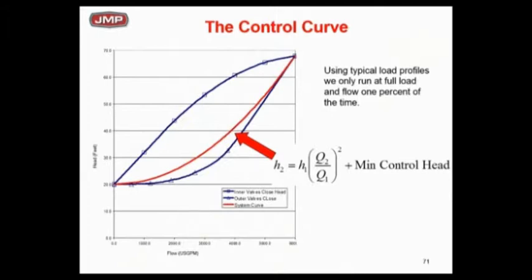If the two-way valves furthest from the pump are asking for the 3,000 GPM, and I don't know, how much head do I need? I just roughly would need, what, about 55 feet? So you could be, at 3,000 GPM, you can be anywhere between 25 feet and 55 feet head requirements on this pump.